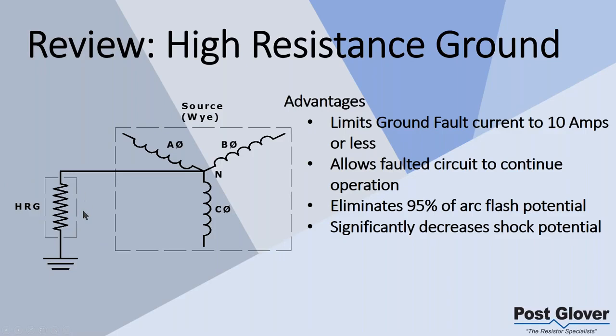That's how it works. For the high resistance ground, IEEE says you have a high resistance ground when the allowed ground fault let-through current is 10 amps or less. Now some of you have used a continuous HRG system that's more than 10 amps. It's kind of a loose definition, to be honest with you, but IEEE defines it that way because they have done studies and testing to determine that at 10 amps or less, there is no damage to your system. I don't believe that testing was done above 10 amps. So just an FYI for you guys.